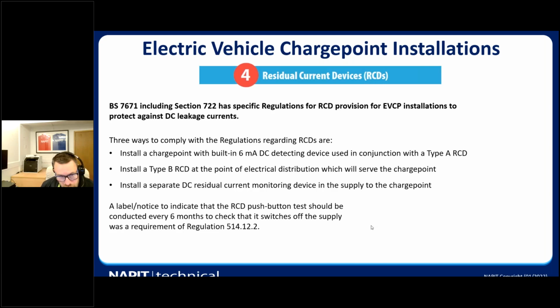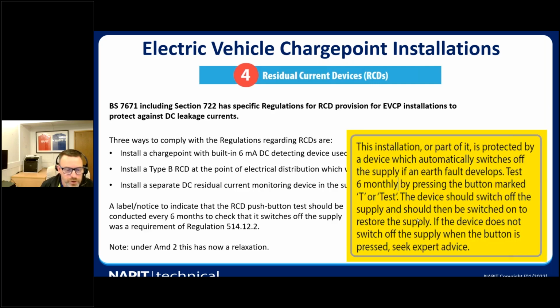And we have a label notice to indicate the RCD requirements for testing the test button every 6 months. Obviously, at the time of the audit, it didn't exist, but under Amendment 2 there is a relaxation within domestic premises: these labels could be omitted if the information is included within the certificate or the EICR. The model forms and the NAPIT forms have that information included in the information for recipients. It shows the labels and the information that has to be provided with the labels. If they are omitted, the information is on the certificates.